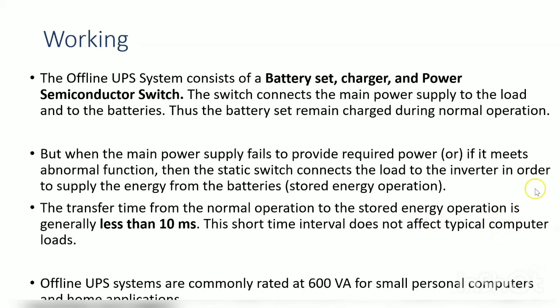The offline UPS system consists of a battery, a charger, and a power semiconductor switch — it is a static UPS. The switch connects the main power supply to the load, and the battery remains charged during normal operation. When main supply failure occurs, the load shifts to the inverter and the battery discharges. The transfer time is generally less than 10 milliseconds, which does not affect typical computer loads.